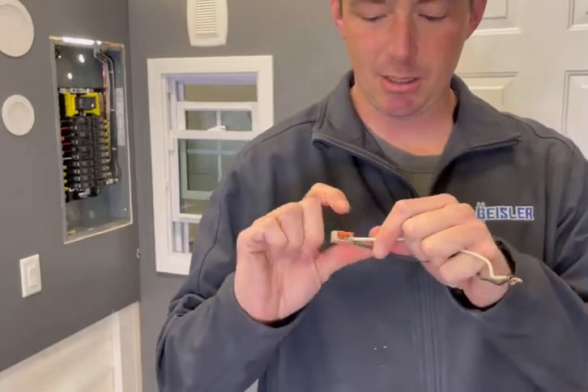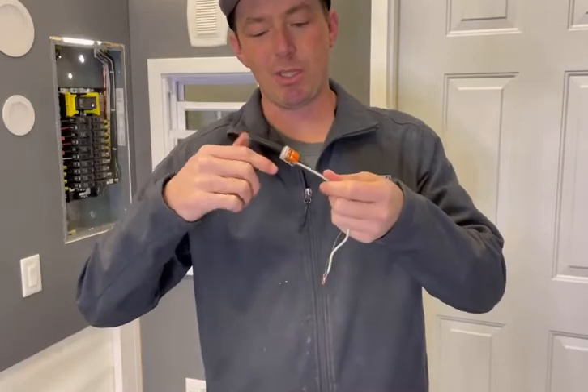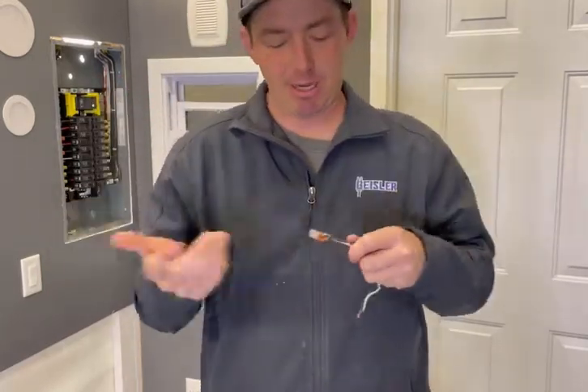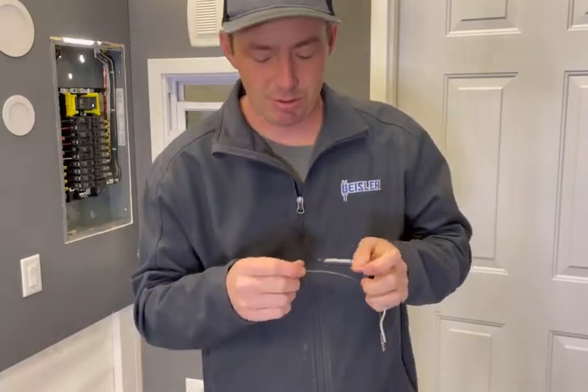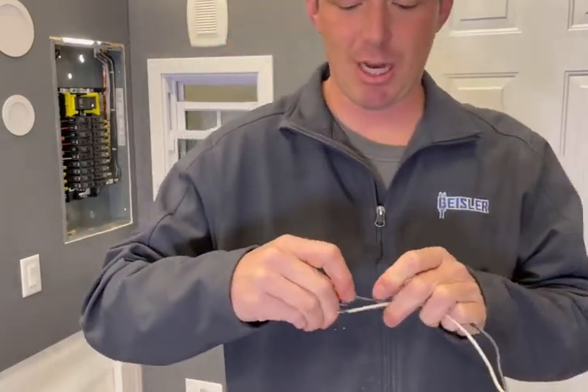These in particular are rated for 32 amps. The difference between this one and the push-style one — you might think it's still just a thin metal strap that doesn't do much. But look at that — I'm pulling on two wires and it didn't come out. You can pull them out, but that took about everything I had, which gives you a good idea of the connection strength.